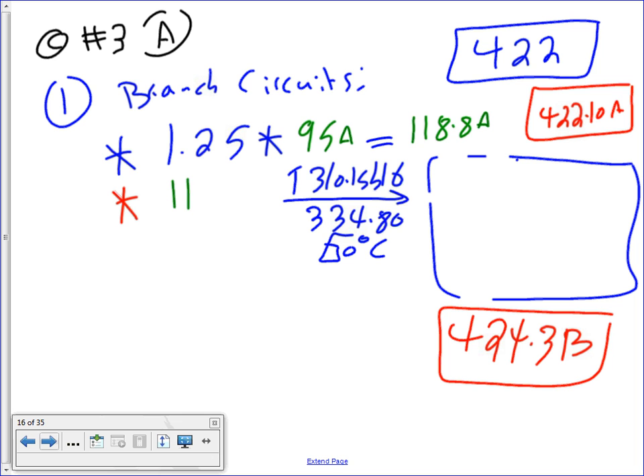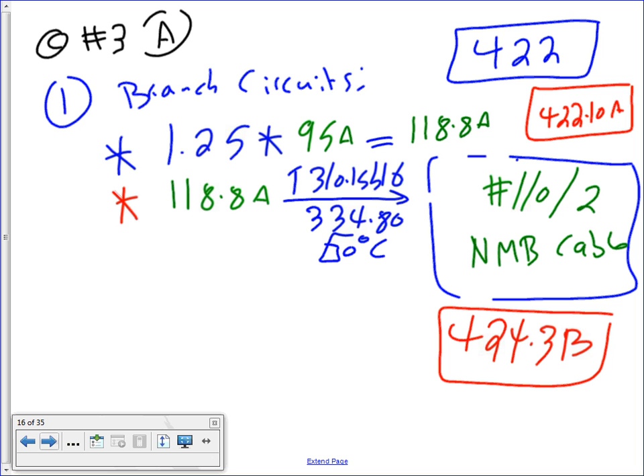You take the 118.8 amps, take it to 310.15, same thing, 60 degree column, that will get you number 1/0. They don't make them in NM cable. NMB cable, I put a question mark here. Be careful, they don't make larger than number 1. So what do you do? By the way, what do you do if they don't make larger than number 1 NM cable? Anybody? We switch to what? MC cable. So you can switch this one to a number 1/0 MC cable. Or AC cable. Since we know they don't make them, let's make this one number 1/0 MC cable.